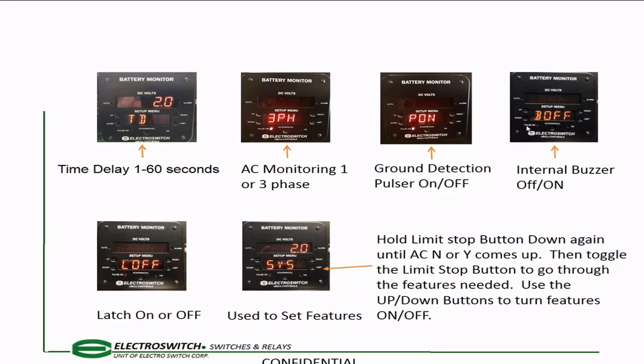Internal buzzer on or off. This is a buzzer that's internal to the meter itself. It's a very shrill sonic alarm that's obnoxious, so most of the time I have it off. Latch on or off. That's if you want to latch in an alarm when it occurs, and then you want to know what the alarm was. It stays there until you go back and hit the reset button in the middle here, and that turns off the alarm.